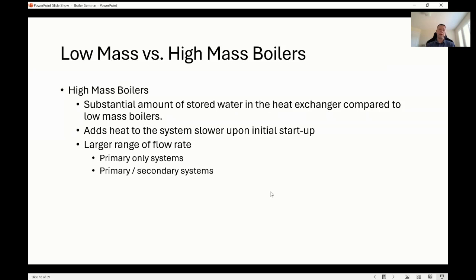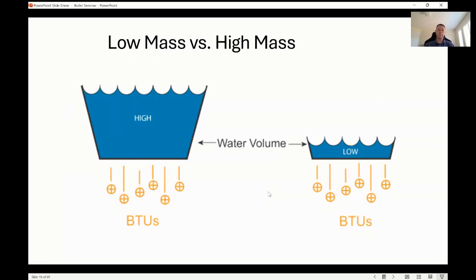Now, a high mass boiler is the opposite. It's a boiler with a lot of water in it. In the stainless steel condensing world, these tend to be fire tube design units. With a fire tube design, the flue products are in the tube, and it's surrounded by a large vat of water, a big tank of water. And this does allow a little bit more flexibility when it comes to flow rates. They generally have a much wider range of flow that they can operate in, and they tend to tolerate variable flow much, much better. As a result of this, you tend to have more selection in your piping schematics. You can do the primary, secondary, which I personally know and love. But a lot of times you can do a primary only system where you have VFDs, just system pumps pumping directly through it.